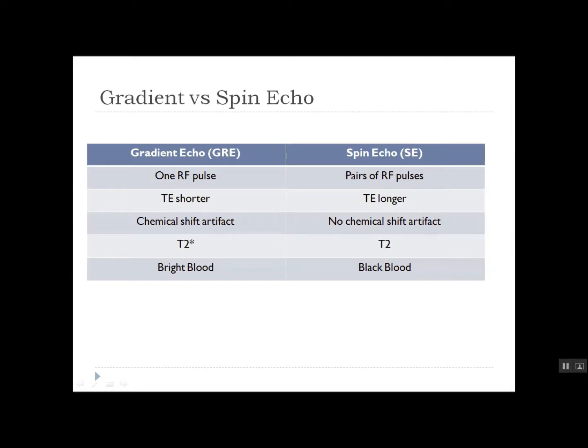The main differences between gradient echo and spin echo can be seen in this table. A spin echo is produced by pairs of RF pulses, but a gradient echo is produced by a single RF pulse with a gradient reversal. Since only one RF pulse is applied, the echo can be recorded much more quickly in a gradient echo sequence, so TE is generally shorter for gradient echo than for spin echo. In gradient echo imaging, the gradient reversal refocuses only those spins dephased by the gradient itself, so phase shifts from magnetic field inhomogeneities, static tissue susceptibility gradients, or chemical shifts are not canceled at the center of the gradient echo as they are in spin echo sequences. Image contrast is dictated not by the true T2 relaxation but by T2-star in gradient echo. As a result, gradient echo sequences are more frequently troubled by susceptibility and chemical shift artifacts.